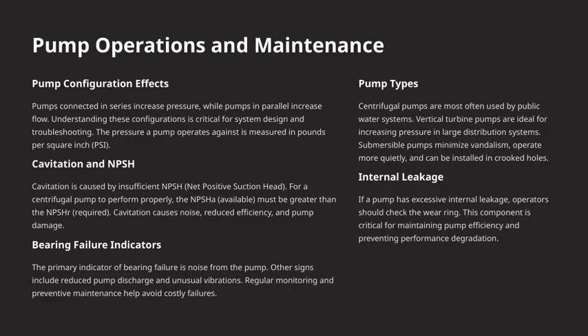Moving on to bearing failure indicators, the most common sign is noise, unusual sounds coming from the pump. Other clues include a drop in discharge flow or strange vibrations. Regular monitoring and preventive maintenance are crucial here. They help us catch issues early and avoid costly failures down the line.